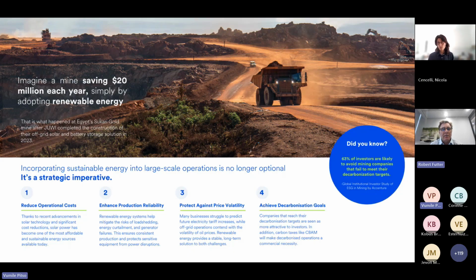Does that mean you're running spinning reserve in the background, or is this project completely renewable when it's fully going at that time of day? I know it's not completely off-grid renewable, but are you still running some spinning reserve even when the battery is dispatching or not? For this project, they do have diesel generators as well, but we are able to feed with BESS. Essentially what we're talking about here is fault ride through for any disturbances on the grid. It's sporadic - you might have a situation where if you don't have PV at that point, you can't only rely on the BESS system to provide stability. You need additional backup to meet grid disturbance requirements.